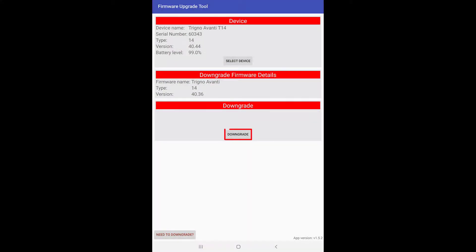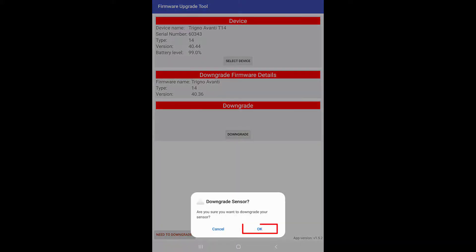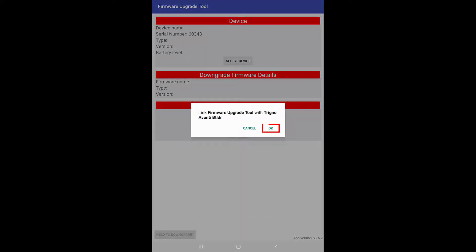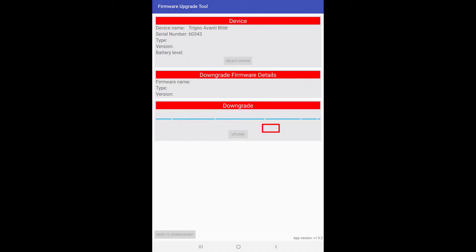In the new screen, click on the downgrade button and then OK for the confirmation prompt. Click OK to link the Firmware Upgrade Tool with Trigno Avanti bootloader.